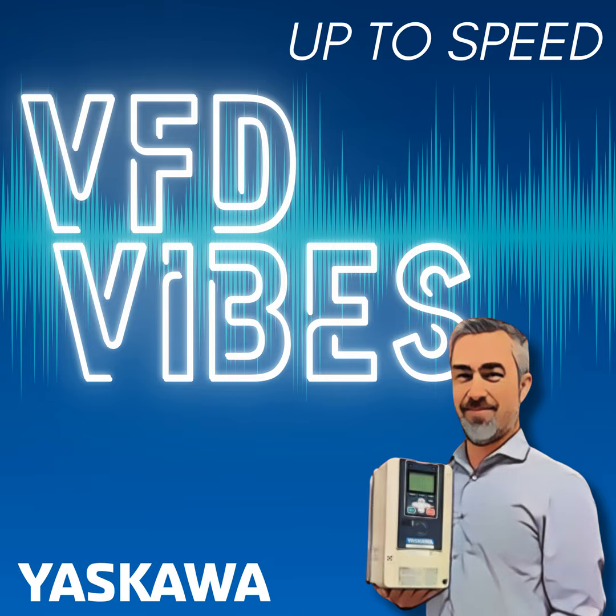Awesome. Again, always appreciate having people with such a breadth of knowledge on the show. And since you are involved in quoting and a lot of that pre-project activity, can you tell us some of the important aspects and things to look for when you're selecting a drive? Sure. Yeah, probably the most important would be addressing your voltage and amperage and enclosure type. Now, let's talk about voltage and amperage first. Generally, there's a 200 volt class and 400 volt class that our customers are going to be dealing with in the lower 48. Now, sometimes 208 and 240 volt or 230 volt are used as the same thing.